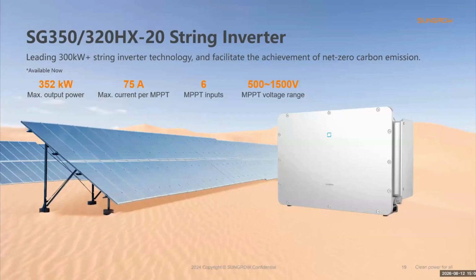So our SG350HX, the second generation, is our mature and available now high power string inverter. It provides up to 352 kilowatts, 75 amps per MPPT, 6 MPPTs, and a voltage range of 500 to 1500 volts. Its key strength is maturity and flexibility. For projects requiring a proven 1500 volt DC and 800 volt AC platform today, I think SG350HX, the second generation, is a strong choice. For future higher power, 1000 volt AC design, the SG510 series is more forward-looking, but it will be available from March next year.